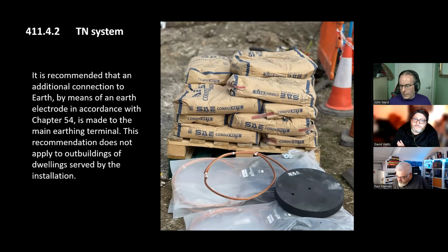An earth electrode can be a nasty old metal rod you ram in the ground, or things like these discs we've got in the picture there. So although it is recommended, put them in. At some point, it's going to say you will put them in. Yeah, it's going in that direction because, as you say, we're taking so many of these other byproduct electrodes out of the building now, and we need this.